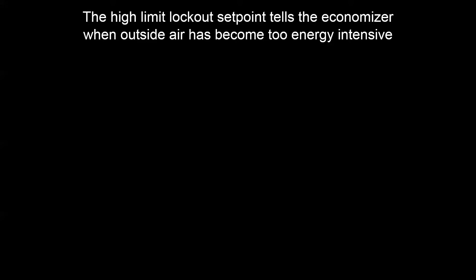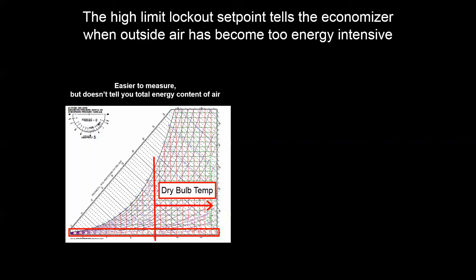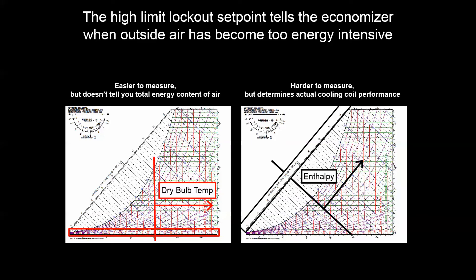The reason we discussed psychrometrics was for moments like this. How can we control an economizer? It boils down to two variables: dry bulb temperature — using sensors that are dependable with low inaccuracy — or enthalpy, which captures true energy content but is harder to measure and carries more potential inaccuracy.